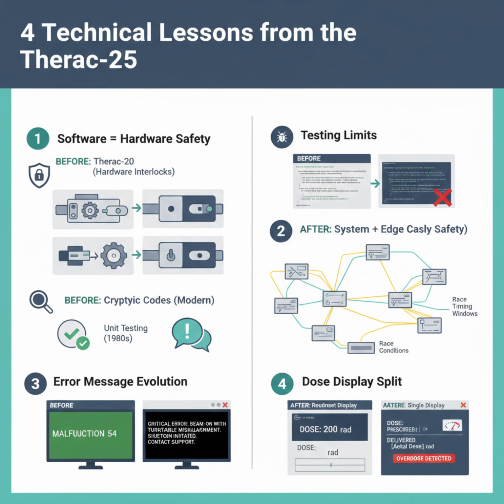This was not a single bug, it was a constellation of design failures. The race condition that allowed beam activation before the turntable was positioned, the absence of independent hardware interlocks that would physically prevent the beam from firing in an unsafe configuration, the cryptic and misleading error messages that obscured the severity of the fault, the decision to display prescribed dose rather than actual delivered dose, the removal of mechanical safety systems without compensating software rigor. Each of these alone might have been survivable. Together, they created a system that could harm patients while assuring operators that nothing was wrong.